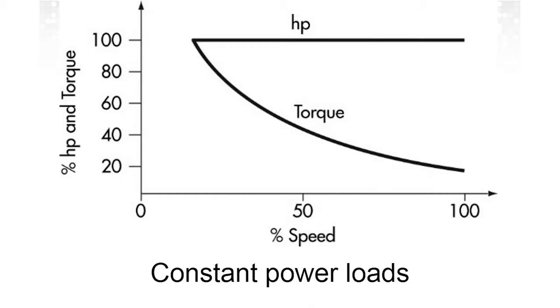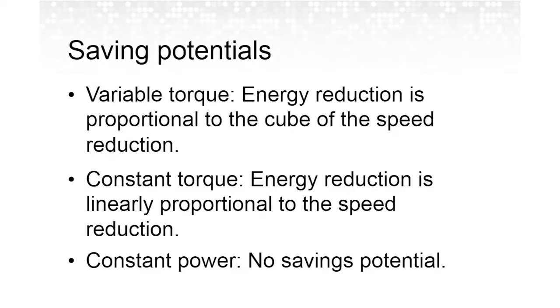For the constant power loads, the horsepower is constant, and then the torque drops off as the speed reduces. So on savings potential, most of the industrial and commercial buildings use variable torque loads. So the energy reduction is proportional to the cube of the speed reduction. So it's a big, big number. For the constant torque, a few of the motors in commercial installations are constant torque, so you get some energy conservation. And then for the constant power, since there's really no savings potential, it works out just as well that most of those motors are in industrial applications.